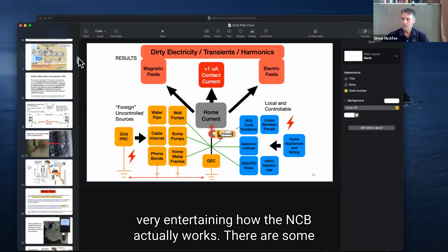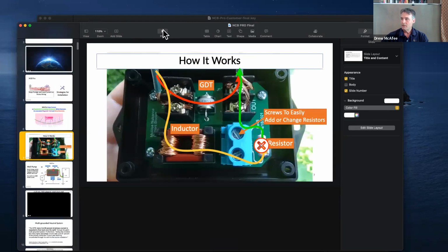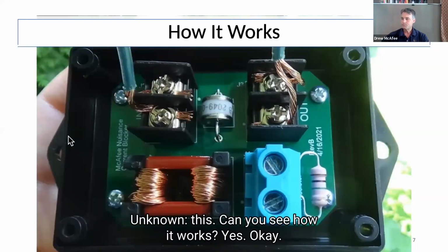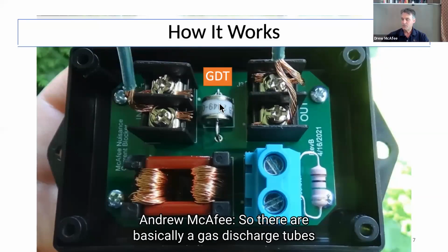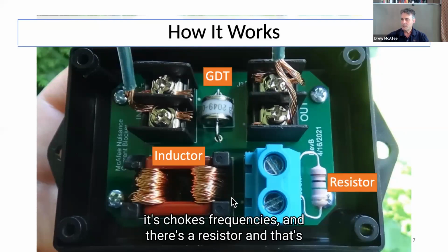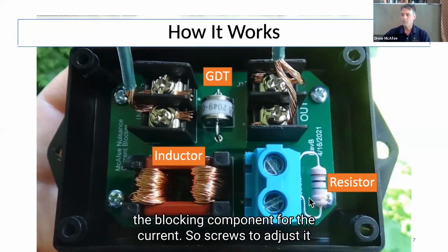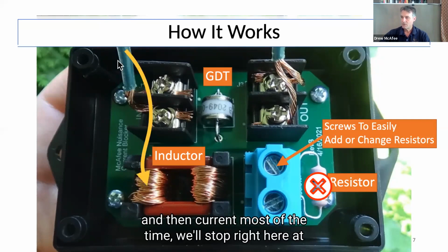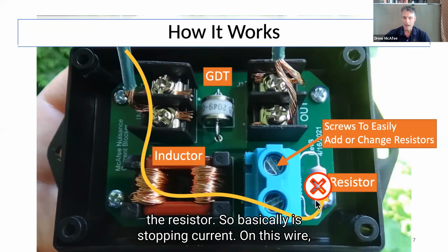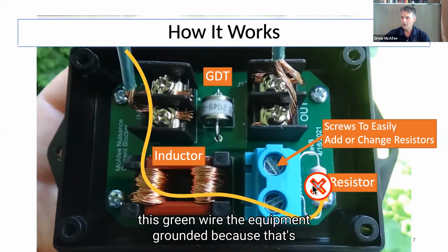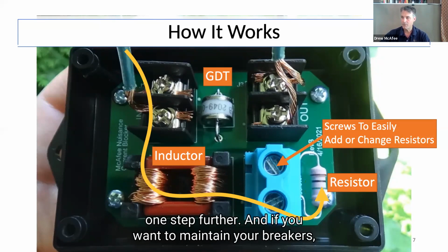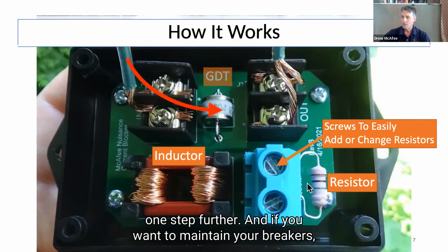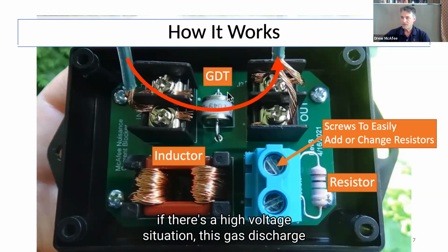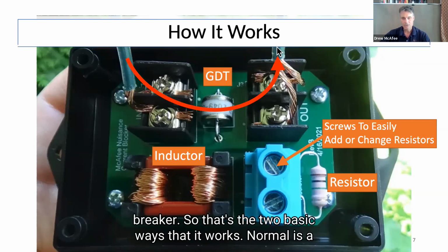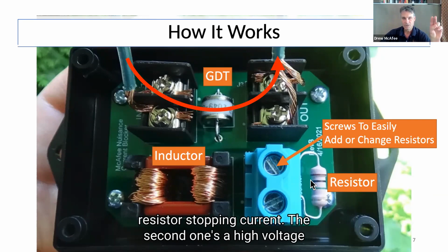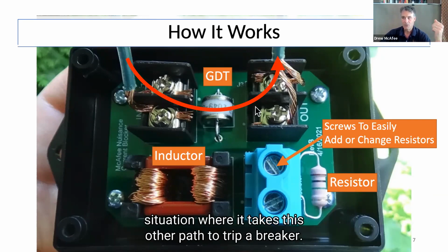How the NCB actually works: there are some components inside that look like this. Can you see how it works? They're basically a gas discharge tube, like a neon light. Then there's an inductor that chokes frequencies, and a resistor, which is the blocking component for the current. It's adjusted so that current, most of the time, will stop right at the resistor, stopping current on this green wire, the equipment grounding. That's the simple version. Now, one step further: if there's a high voltage situation, the gas discharge tube lights up and the current goes directly back and trips the breaker, maintaining your breakers. So those are the two basic ways it works: normally a resistor stops current, and in a high voltage situation it takes this other path to trip a breaker.